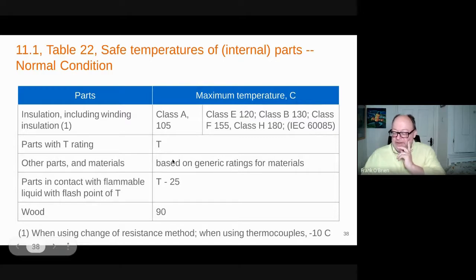So parts have their own ratings and they become the limit. Boards and wiring have their limits, or if they don't, there's some generic limits. Parts in contact with flammable liquid with a flash point, you'd want the temperatures to stay at, not just under the limit, but 25 under the limit. And then wood's allowed to be 90, like we use wood a lot. That's an oldie but goodie.